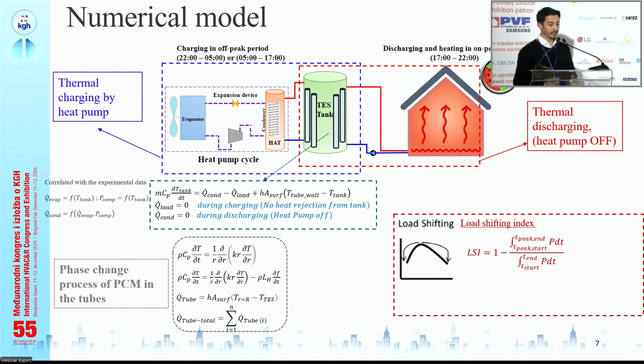And most importantly, we also defined a load shifting index in order to quantify how much load we shifted from on-peak periods to off-peak periods by using the pre-stored heat inside the thermal energy storage tank. So this is the measure for us of how much time we did not need to operate the heat pump for the building heating.